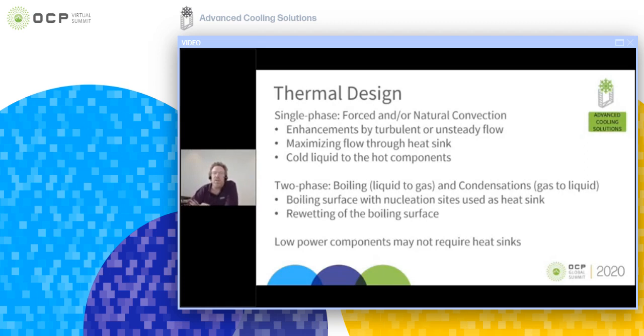For two-phase immersion, the approach is different compared to single-phase immersion. In two-phase immersion, the immersion liquid has a relatively low boiling point. So when the liquid reaches the hot components, the liquid is experiencing a phase change to gas, and there's a boiling going on. The gas rises to the top where the condenser is located, and the condenser cools down the gas, and it's returned to liquid and can be reused for the cooling process. To make this process as efficient as possible, the heat sinks on the high-powered components should be replaced with simplified heat sinks that are flat plates with boiling enhancement coating.